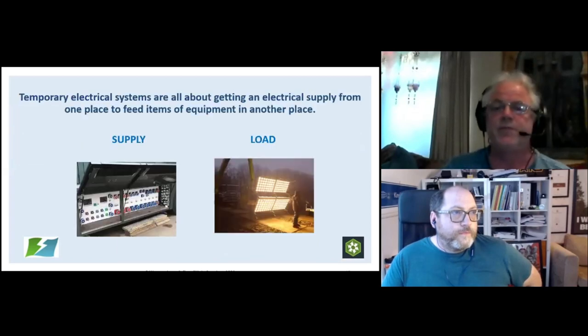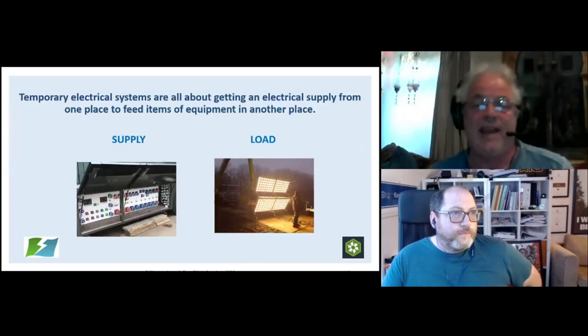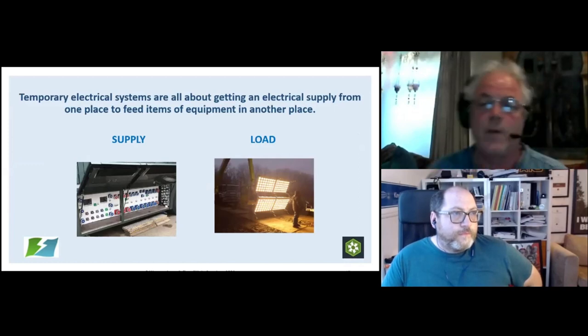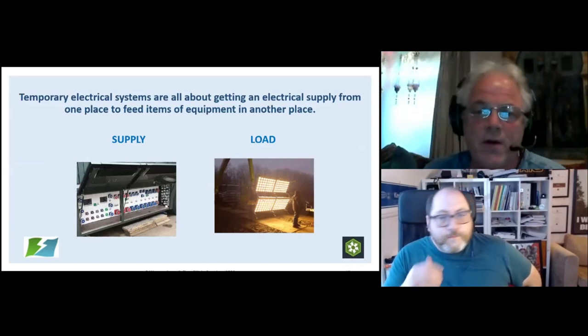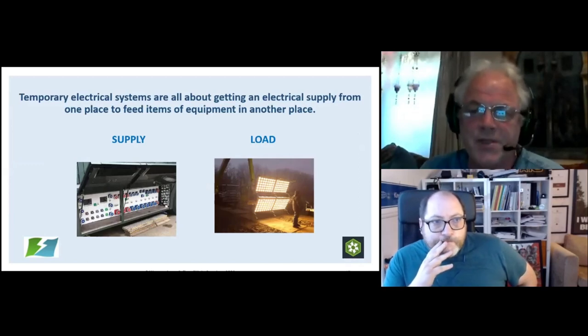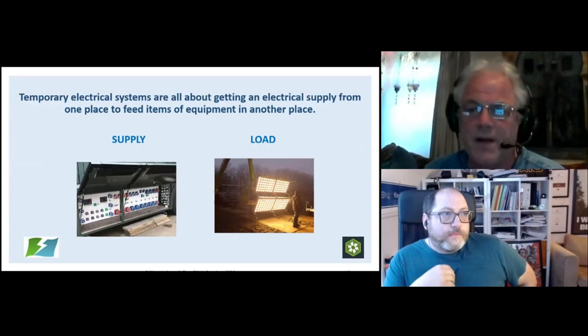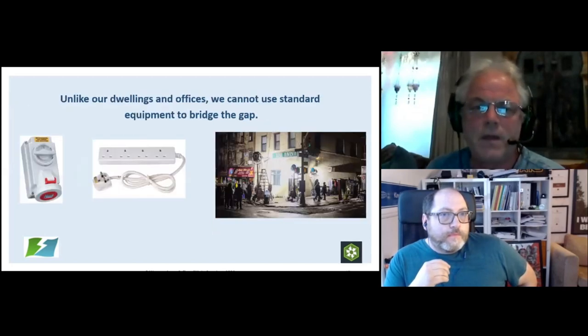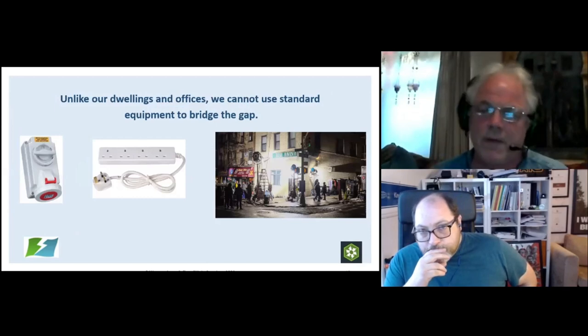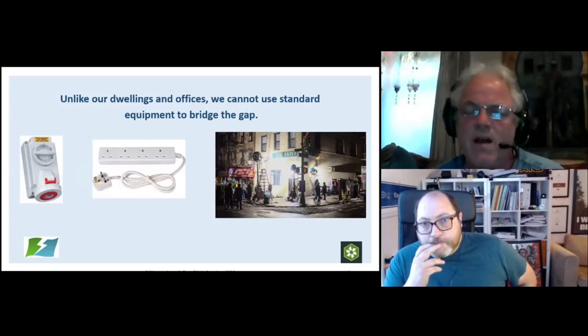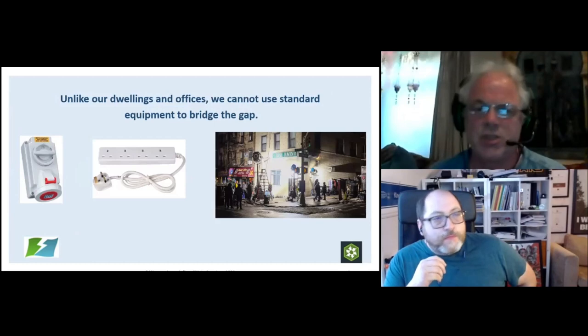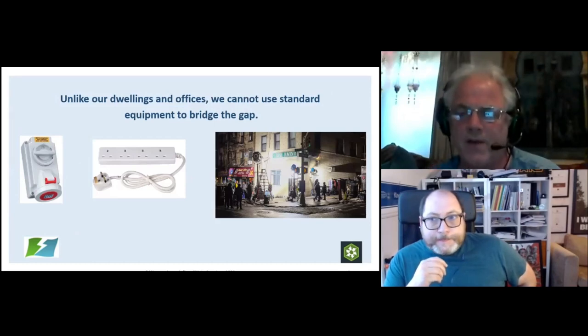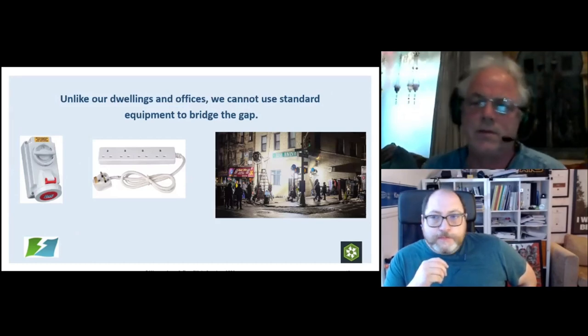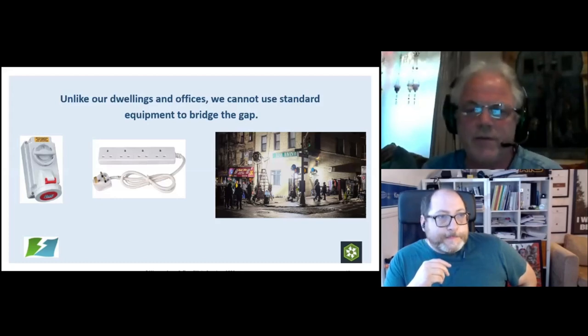So what are temporary systems all about? Well, it's all about getting electrical supply from one place to feed equipment in another place. You've got a supply, you've got a load, and you've got to put a system in which will allow you to run that load from that supply in a safe and efficient manner. Unlike in our dwellings and in our offices, we can't use standard extension leads to bridge the gap. Quite often the amount of power that we're going to need is quite a lot, and the idea of doing it with 13 amp extension leads and similar is just totally unmanageable.